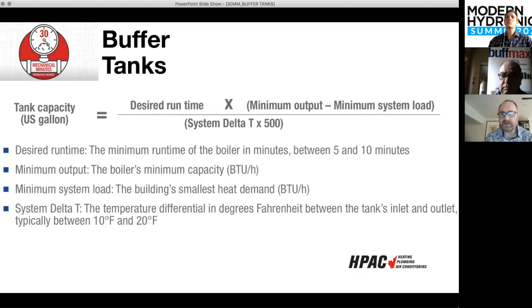If you go through your math, I would say that we want to have at least a minimum runtime of 5 minutes. By doubling that runtime, there's a direct correlation with the size of my tank. I would actually be doubling the size of my tank. I would want to see at least a 36-gallon buffer tank in that small example we gave there. So okay, I hope I didn't confuse too many people. The math can be daunting, but it's basically following it step by step, and it's very simple to do.